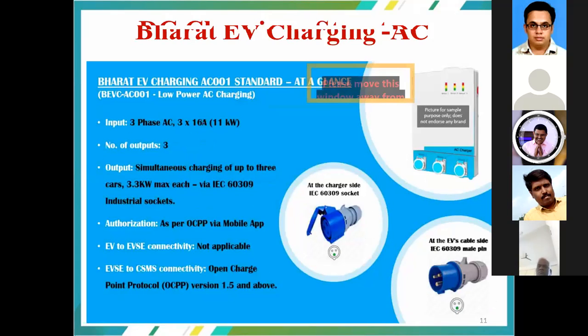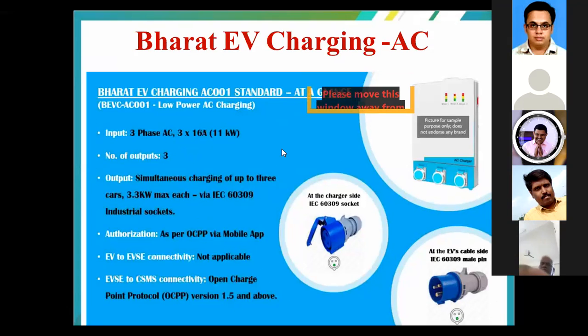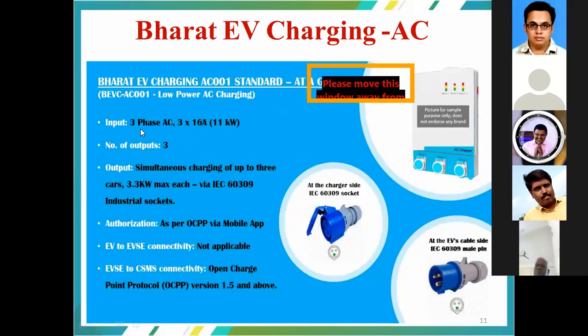That is the Bharat EV charging, Bharat EV charging DC. And there we are going to have the DC 001 standard, which is meant for India. And the input voltage, output kilowatt, number of outputs, the authorization, and the EV to EVSE connectivity are as mentioned in the PPT. And next one is the Bharat EV charging standard AC001, which is meant for the AC supply voltage. And again, the input supply is going to be 3-phase, and the three phases are going to carry a maximum of 16 amperes, and the total power rating is going to be 11 kilowatt. Again, the number of outputs is going to be 3. Output is simultaneous charging of up to 3 cars of 3.3 kilowatt maximum each.